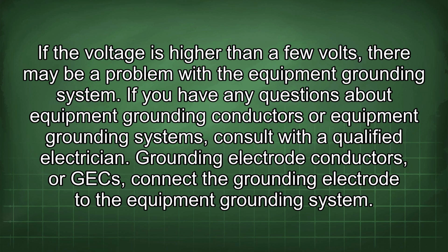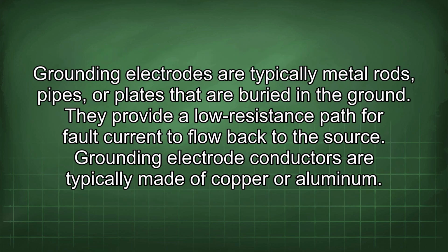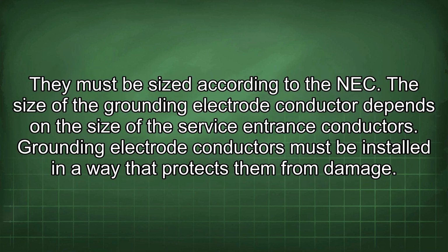Grounding electrode conductors, or GECs, connect the grounding electrode to the equipment grounding system. Grounding electrodes are typically metal rods, pipes, or plates that are buried in the ground. They provide a low resistance path for fault current to flow back to the source. Grounding electrode conductors are typically made of copper or aluminum. They must be sized according to the NEC. The size of the grounding electrode conductor depends on the size of the service entrance conductors.